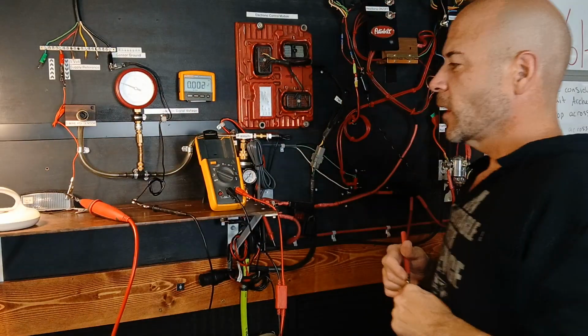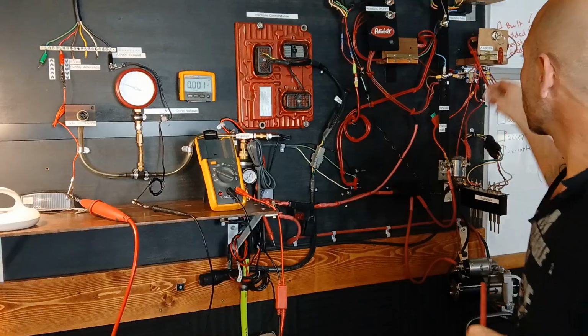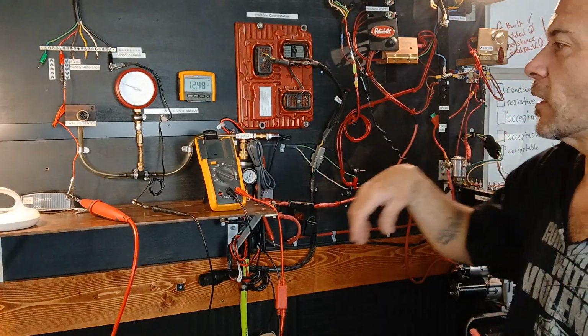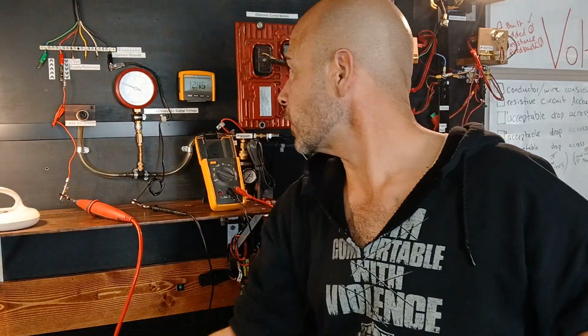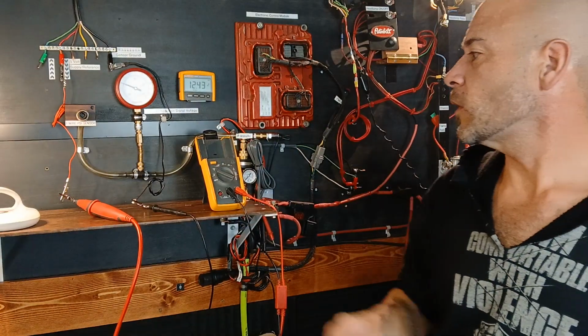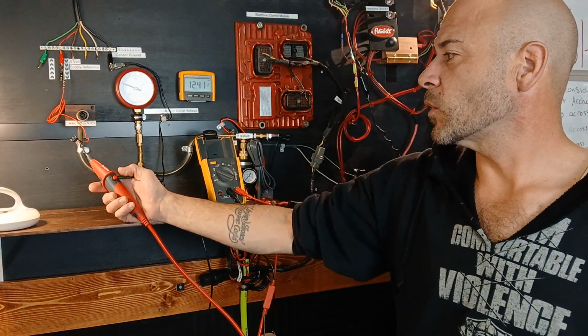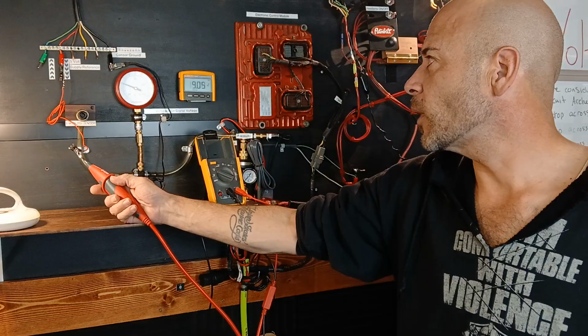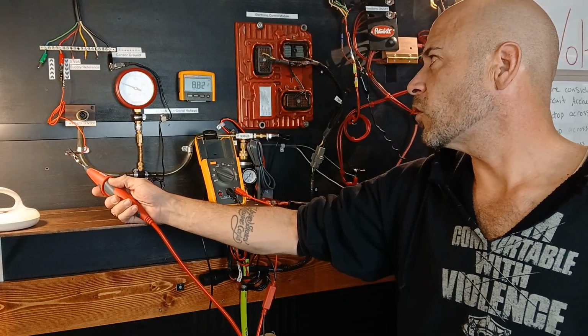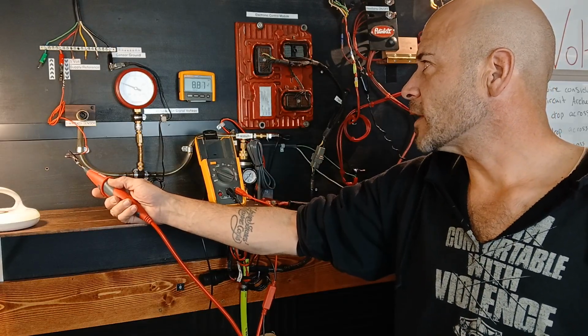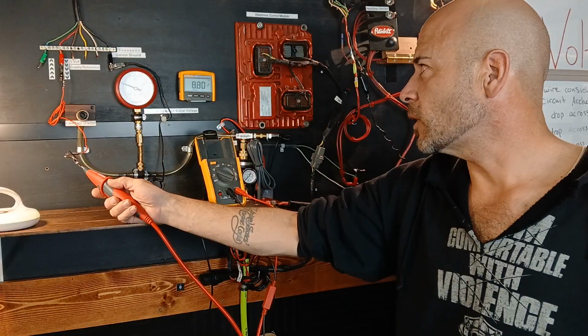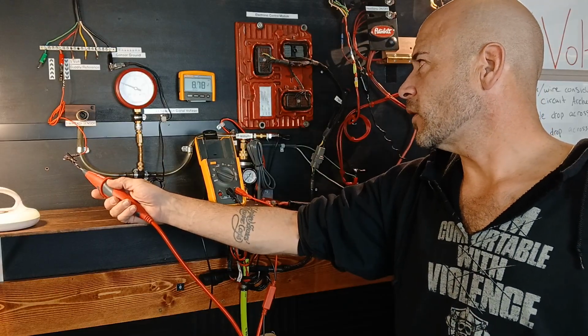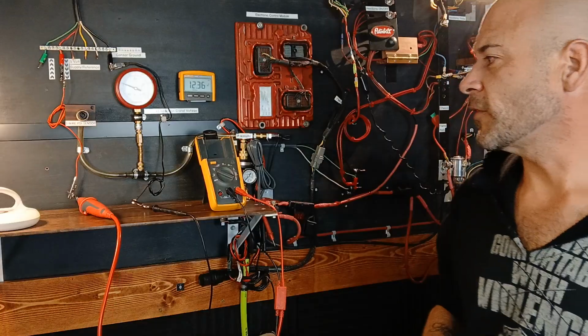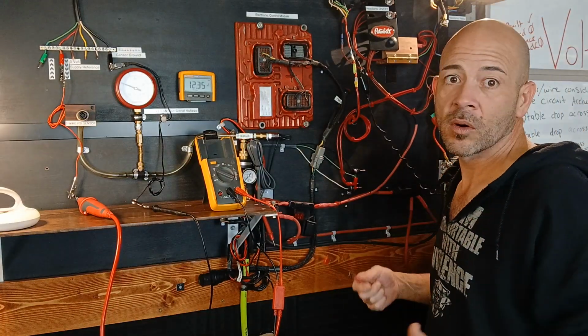Now we're looking at that same power and ground that's available, but the load is out of the way, we've removed it. We have that same 12.4. When we use this load probe, the Bees Knees 2000, and push the button, it applies a 25 ohm resistor, a half amp load, to that same circuitry. Right now we have 8.78, so we definitely have a problem with either our power or our ground to the light.